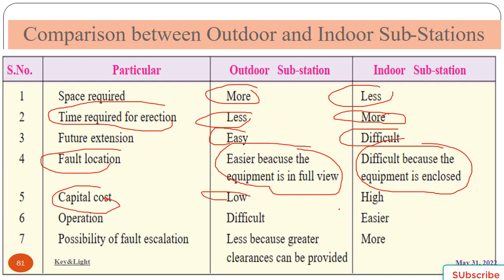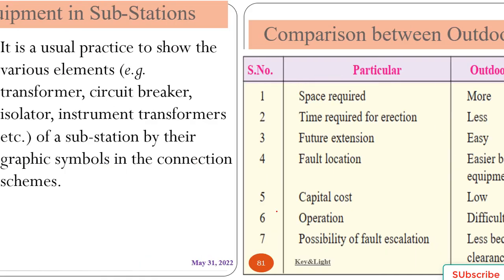And capital cost: in outdoor it is low and in indoor it is high. Operation: it is difficult to operate in outdoor and easier to operate in indoor. Possibility of fault escalation is less in outdoor because greater clearance is provided, and it is more in indoor.